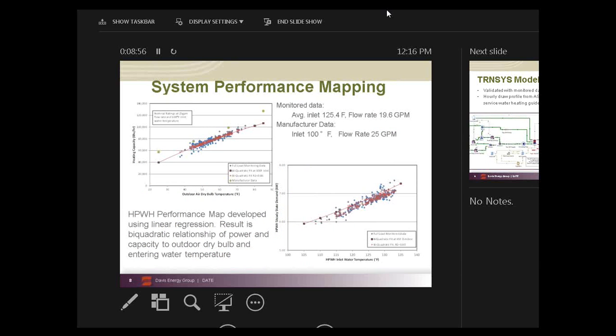The data from the monitoring period was then compiled and filtered for full load operation to determine the relationship of capacity and power to both entering water temperature and outdoor temperature. The relationship was developed using linear regression, and the resulting map was formatted in such a way that we could use it with TRNSYS model for simulations. TRNSYS is a transient simulation suite.